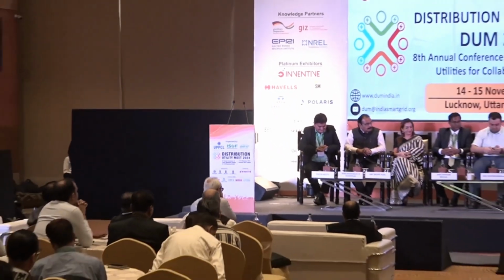Three takeaways. One, a 4% forced outage rate is excessive. Generally, even at 1%, a project is initiated to ask why we are hitting 1%, whether it's due to age, lack of maintenance, or whatever. DTs generally never get maintained, they're all run to fail. So 4% is definitely high; 0.7% should perhaps be the norm.